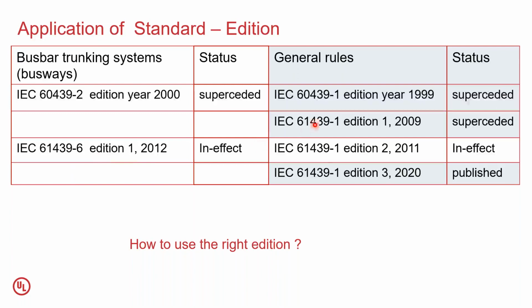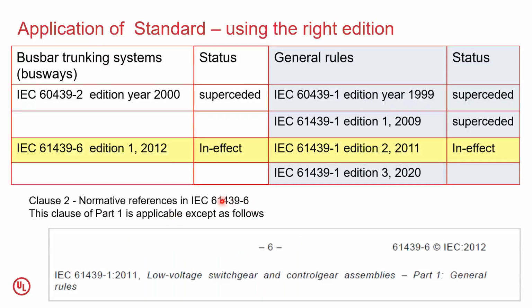Now let's understand which part 1 edition we need to use when it comes to 61439-6 application. It is very easy. When you go to the specific part standard, in this case the normative references in 61439-6, it very clearly specifies which edition you are supposed to use. So this clearly specifies that for the 2012 version of 61439-6, you are supposed to refer to the 61439-1 2011. Even though there is an updated version, which is the 2020 version, you are not supposed to use that unless that gets reflected in your specific part standard. So in summary, the part 1 edition that has to be used is actually brought out in the specific part standard. I hope you understood how to apply the specific edition and also how to refer to the specific part 1 edition as well.